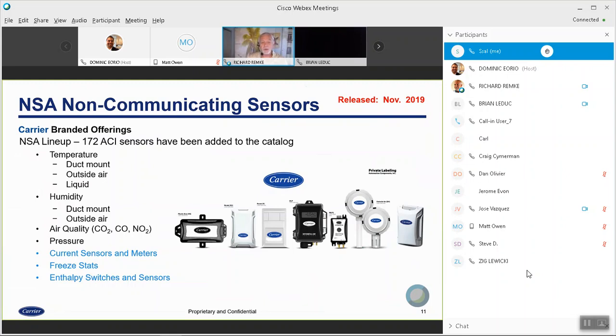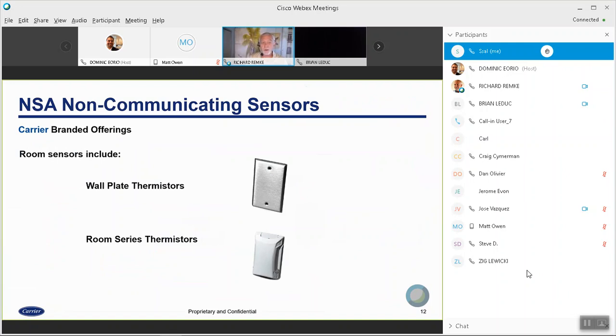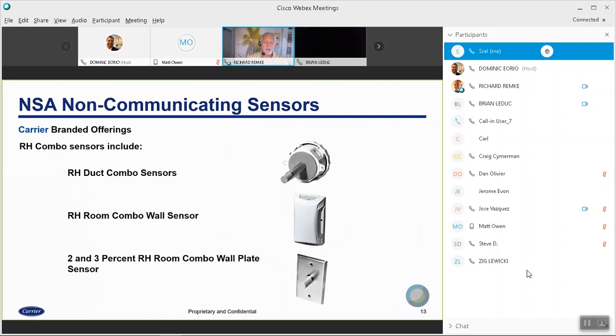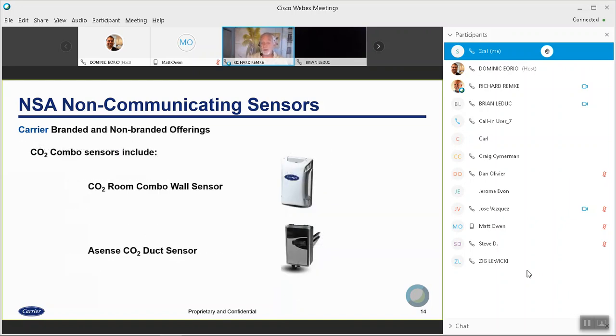Now we give you a choice, especially for temperature and humidity. But we bring some other things to the table with the NSA line that BAPI just didn't have. Current sensors and meters, freeze stats, enthalpy switches, sensors, things like that. So just to quickly go through some of these, you can get Carrier branded offerings on wall sensors, room thermistors. You can get RH combo sensors, duct sensors. We have 2 and 3% RH sensors, so we can cover multiple applications. We have CO2 sensors, and there's several of those. We have a combo wall sensor.